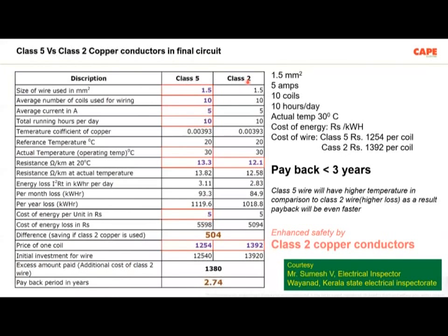He helped me, or he made this particular table, and finally our calculation, for example, 1.5 square millimeters of wire, imagine 5 ampere current flows through this particular wire. We took a case of 10 coils, approximately, maybe typically for a small scale industry or a small house, 10 hours per day it is working with an actual temperature of 30 degrees centigrade. So this actual 30 degrees centigrade, we took these values in a very, very moderate way.